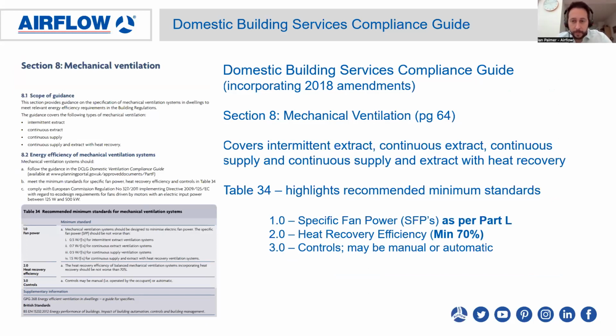So again, because it's now in Part L, it does refer to the specific fan powers, which we touched on earlier. But it also focuses on minimum heat recovery efficiency. So if you're using an MVHR system, the minimum efficiency needs to be 70% or higher. And it also covers the controls, saying that these mechanical ventilation systems may be manually controlled or automatic.